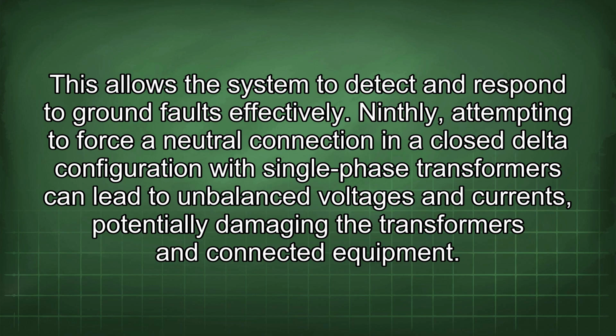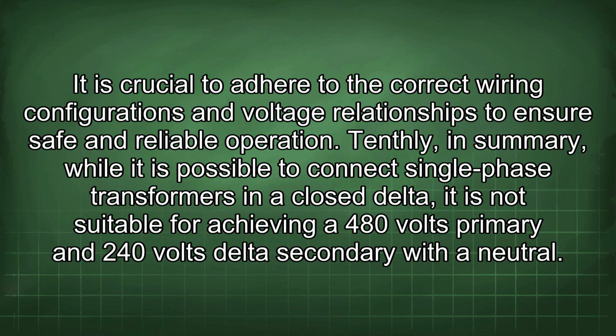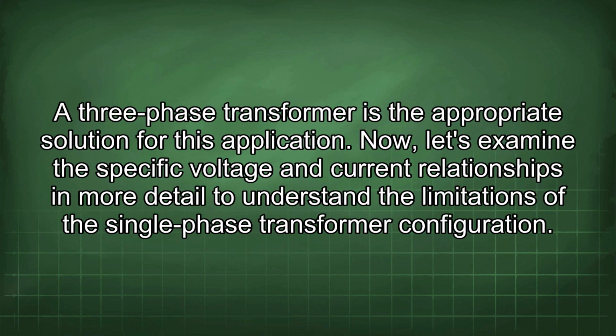Ninthly, attempting to force a neutral connection in a closed delta configuration with single-phase transformers can lead to unbalanced voltages and currents, potentially damaging the transformers and connected equipment. It is crucial to adhere to the correct wiring configurations and voltage relationships to ensure safe and reliable operation. Tenthly, in summary, while it is possible to connect single-phase transformers in a closed delta, it is not suitable for achieving a 480 volts primary and 240 volts delta secondary with a neutral. A three-phase transformer is the appropriate solution for this application.